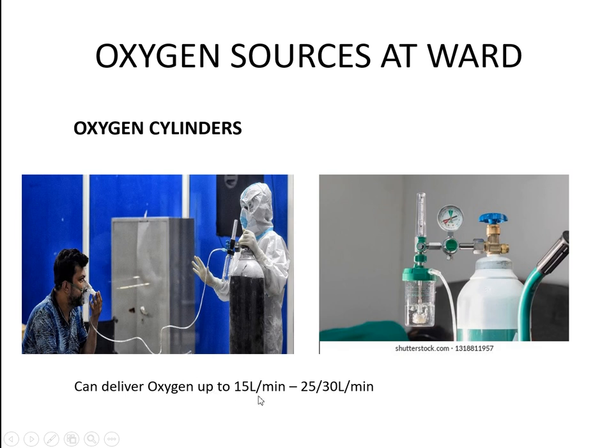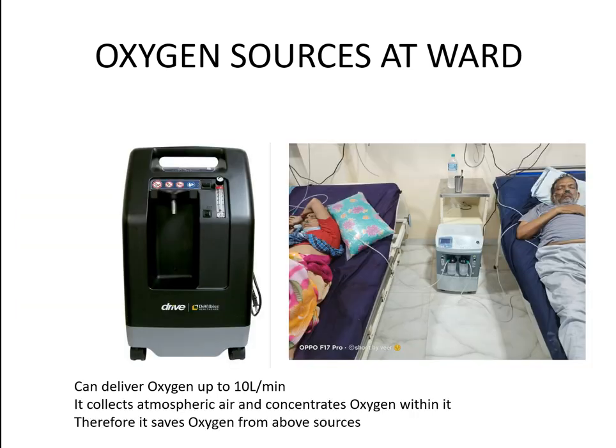Here also we can deliver 15 to 30 liters per minute, depending on the flow meter, right? Obviously most of our Sri Lankan hospitals, most of our COVID-19 treatment wards, have this method of delivering oxygen. They have a need for oxygen cylinders at the moment, as we consume a lot of oxygen per day, as I mentioned at the very outset of my presentation, right? This is another efficient way of delivering oxygen. In all the past slides I showed you, the oxygen source is either a liquid oxygen store or a gas oxygen cylinder. In those plants they have oxygen, and then this oxygen is carried to the patient.